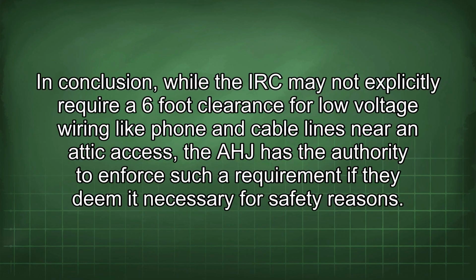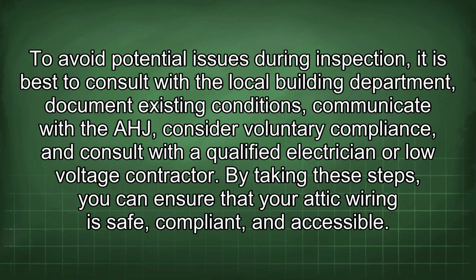In conclusion, while the IRC may not explicitly require a 6-foot clearance for low-voltage wiring like phone and cable lines near an attic access, the AHJ has the authority to enforce such a requirement if they deem it necessary for safety reasons. To avoid potential issues during inspection, it is best to consult with the local building department, document existing conditions, communicate with the AHJ, consider voluntary compliance, and consult with a qualified electrician or low-voltage contractor. By taking these steps, you can ensure that your attic wiring is safe, compliant, and accessible.